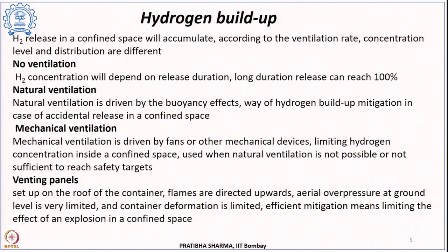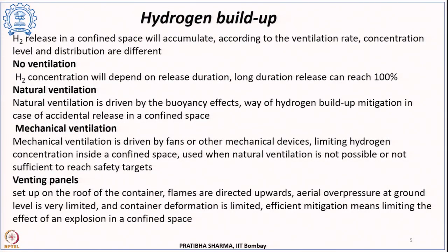Now as mentioned, if hydrogen release takes place in a confined space, it will start accumulating and that will build up hydrogen concentration in that confined space. Depending upon the ventilation rate, the concentration level of hydrogen as well as its distribution in that confined space may vary. Let us say if there is no ventilation, in that case hydrogen will keep on building, and depending upon for how long it has been released before being shut off, it can even reach a concentration level of 100%. If natural ventilation is present, because of the buoyancy effect it will be driven out. So natural ventilation, if present, is a way to mitigate such hydrogen buildup related catastrophe, and in that way it can mitigate the accidental release in a confined space.